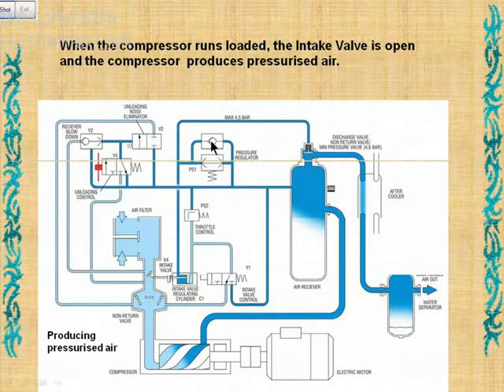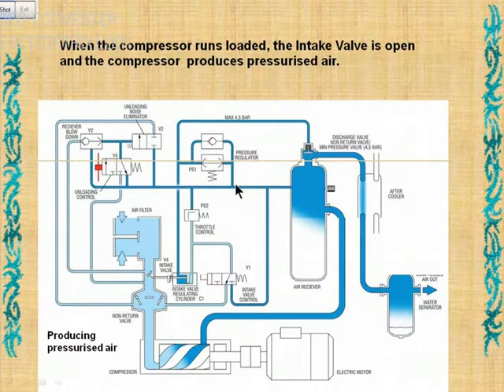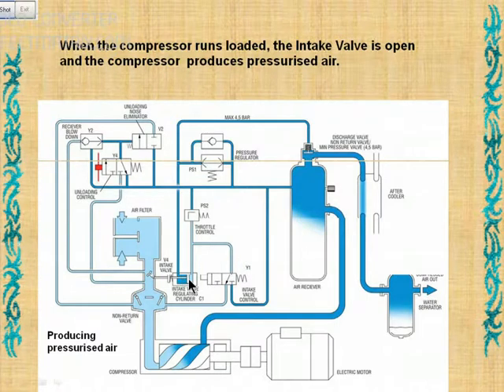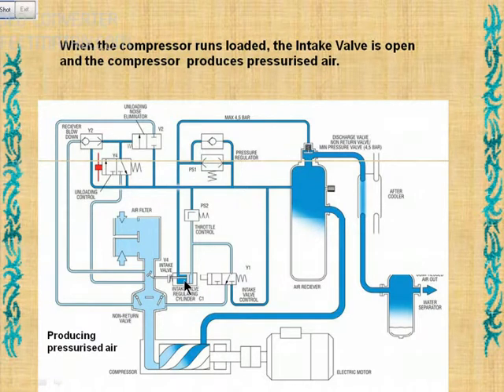We have a pressure regulator valve here — this is the pressure regulator. Once the pressure increases, the pressure will go through this. We have a throttle control, so it will pass through and push the cylinder back, so that the pressure in the cylinder air receiver does not exceed limits. This cylinder will be pushed either this side or that side according to the pressure.